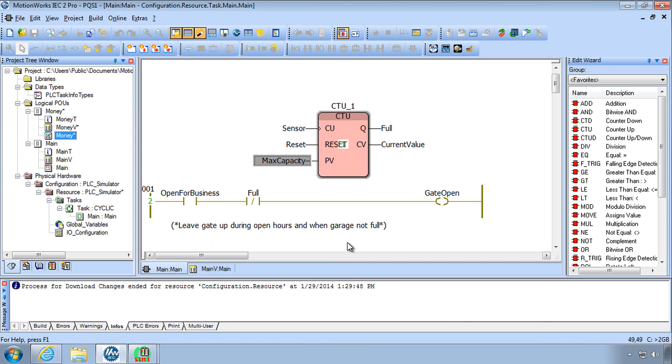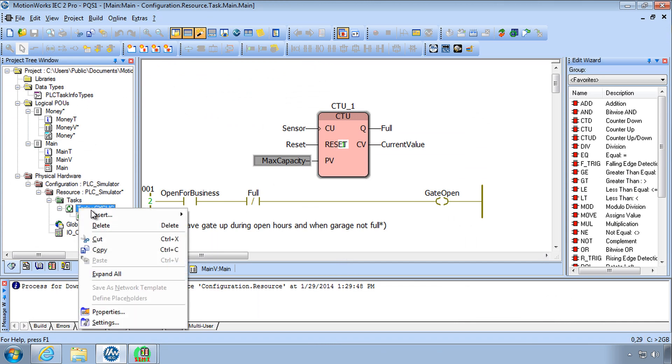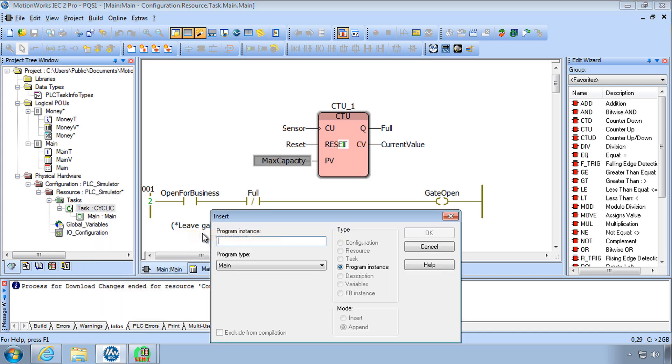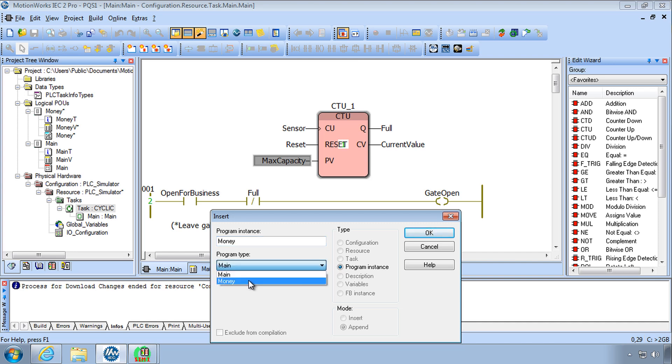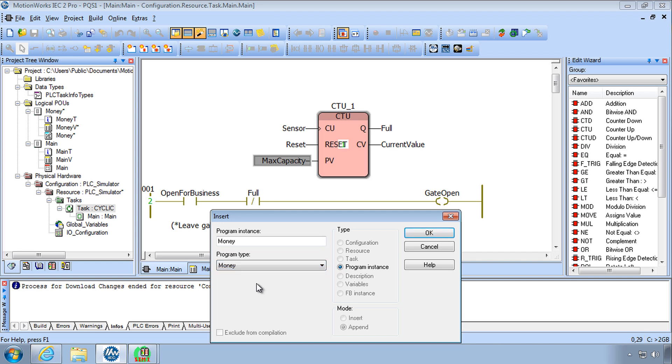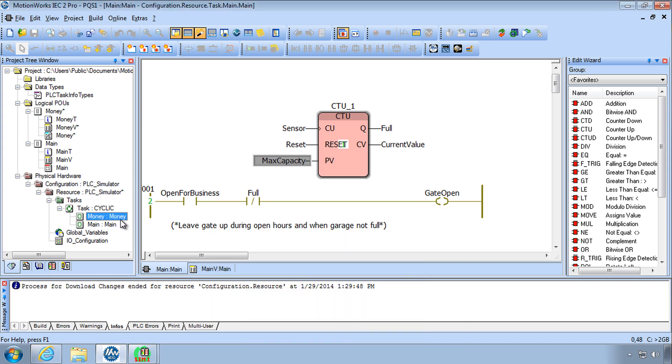And so this is the second step. Anytime you insert a POU, a program POU runs in a task and so you'll have to insert it manually into one of the tasks or if not create a new task. In this example we will add it to the existing task by right-clicking insert program instance. So let me demonstrate that. The POU's name is money. Right-click insert program instance into this task. I'm going to call it money. Now don't stop here. How many times have I seen people type in the name and click OK? That's not right. You have to choose the program type.